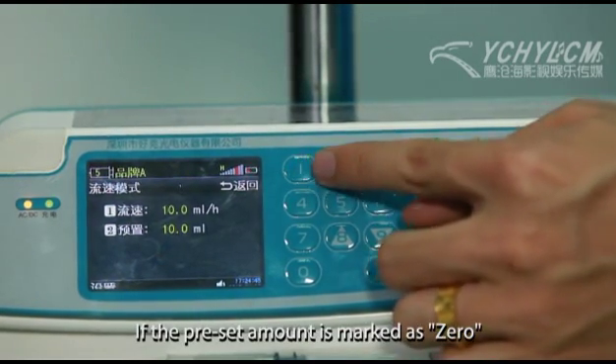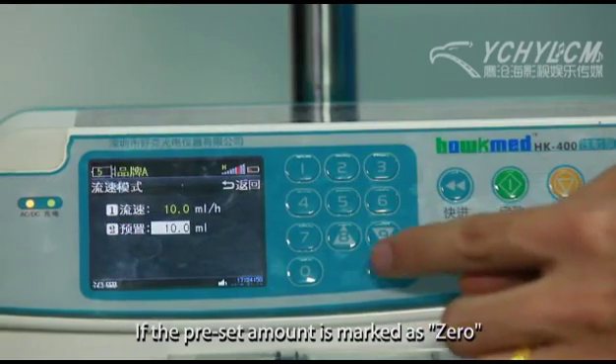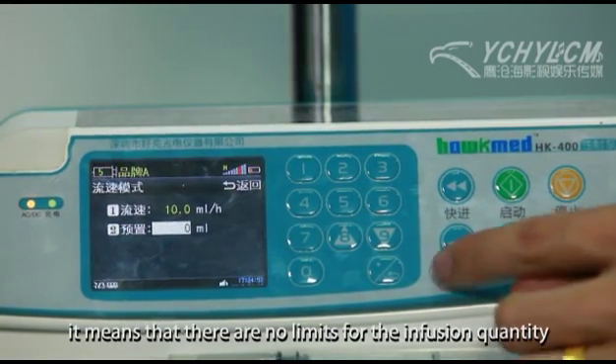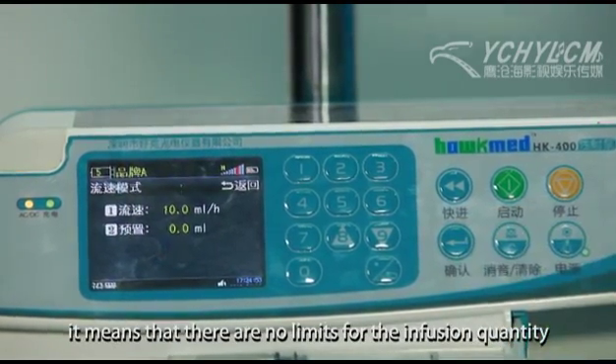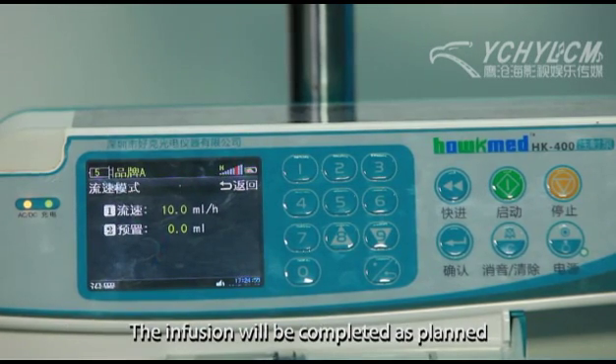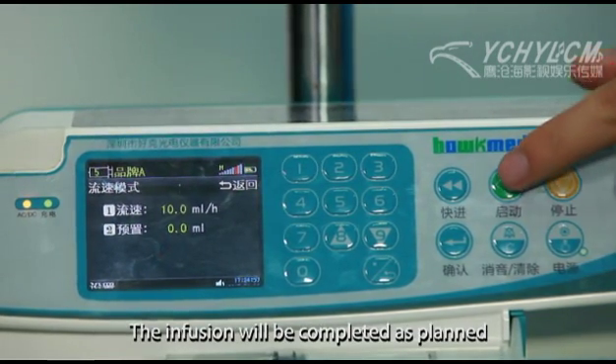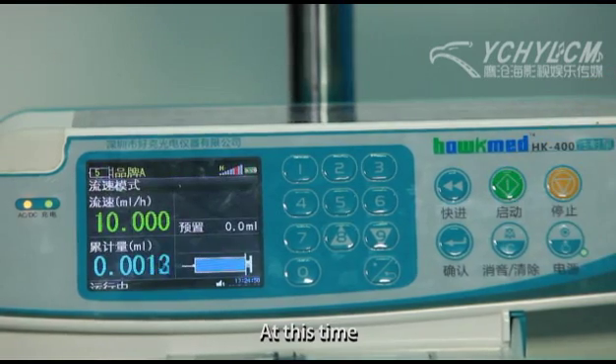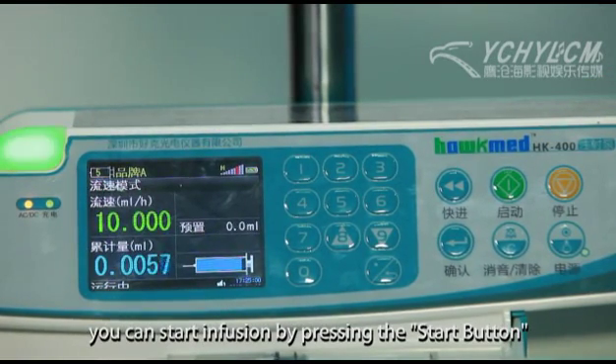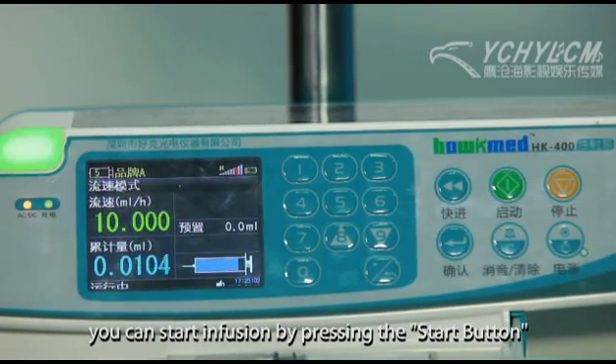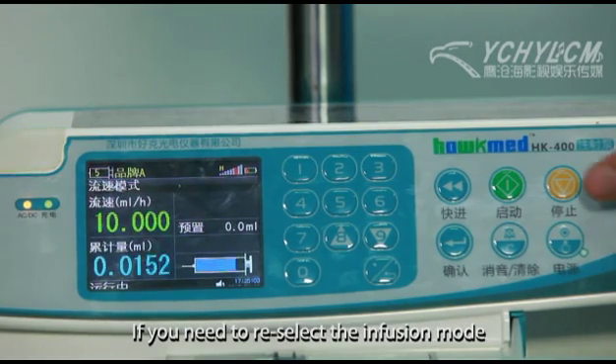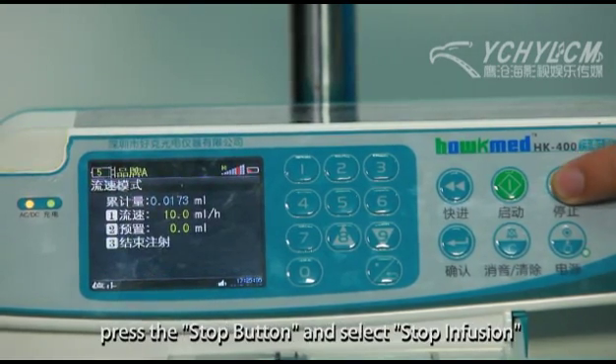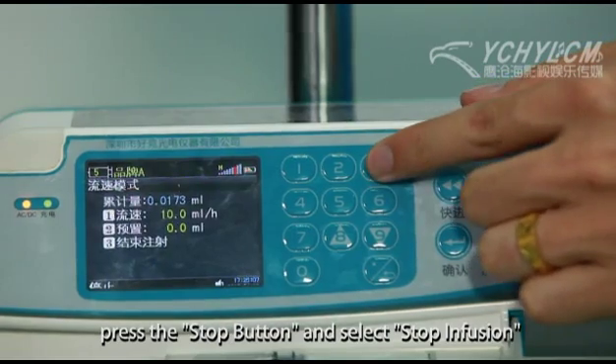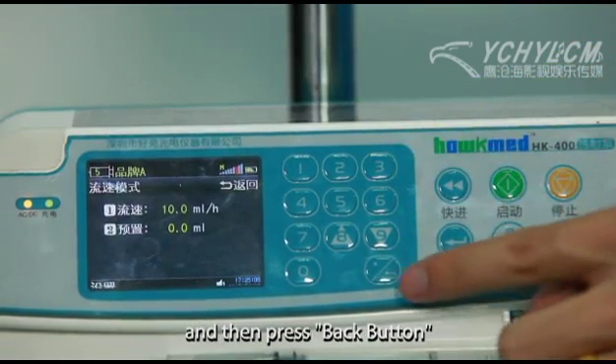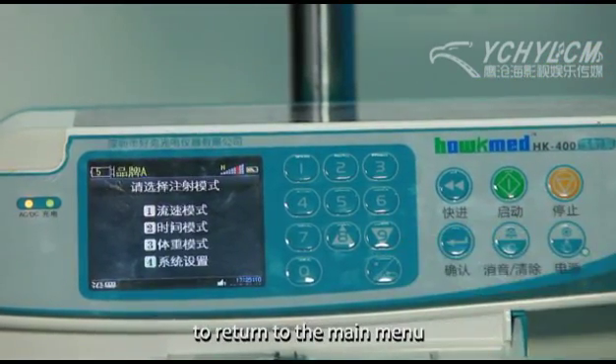If the preset amount is marked as 0, it means that there are no limits for the infusion quantity. The infusion will be completed as planned. At this time, you can start infusion by pressing the Start button. If you need to reselect the infusion mode, press the Stop button and select Stop Infusion, and then press the Back button to return to the main menu.